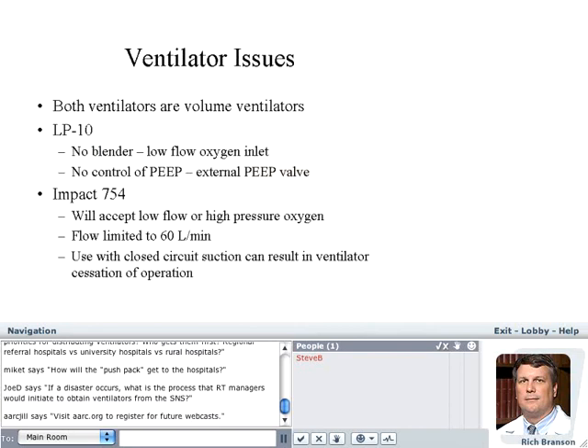And so if you have a patient who's very actively breathing, it may be that the work of breathing could be very high. And so I suspect that we will ventilate most people in assist control and probably give them reasonable amounts of sedation. The other thing I wanted to talk about is that when the 754 was designed, there was no such thing as closed circuit suction catheters. And the 754 has a particular system safety: if for some reason the pressure in the circuit falls below negative 10 centimeters of water pressure for longer than 2 seconds, the machine will turn itself off.